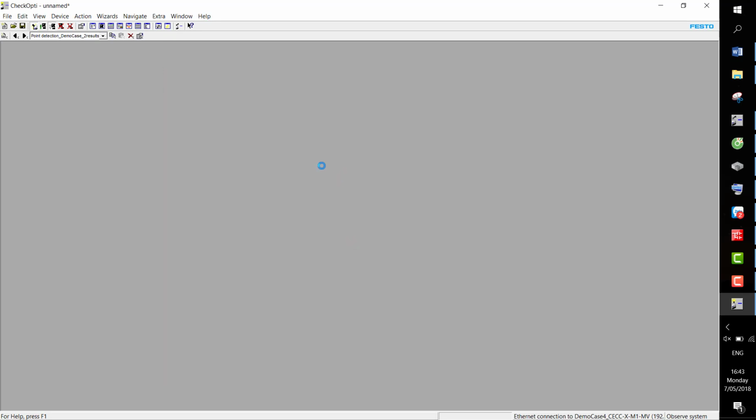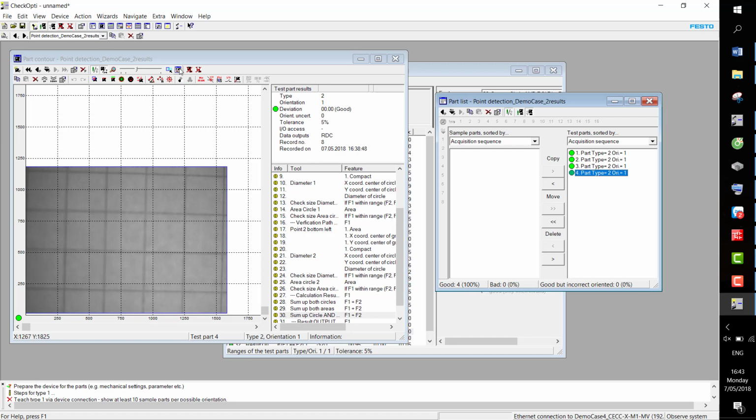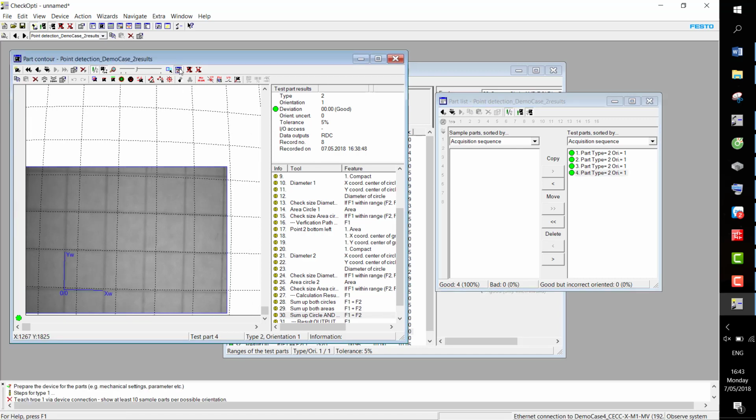So once you calibrated it, it will look somewhat like the pattern. Then you can use this to capture, let's say, your vision detecting your workpiece, the part position, even the orientation. Then read this position back to the PLC for whatever movement after that, like when you pick it up, correct it and place it somewhere else. And it's in millimeter, right? Millimeter. Yes, millimeter.